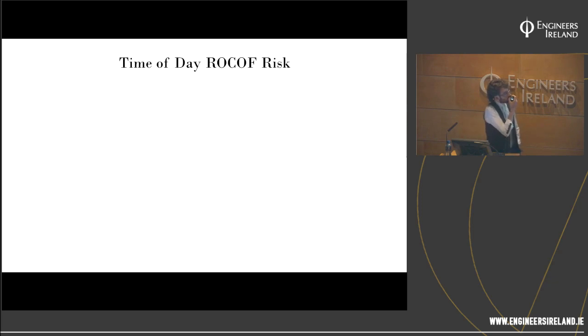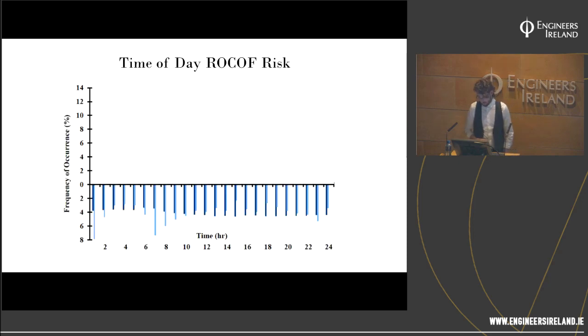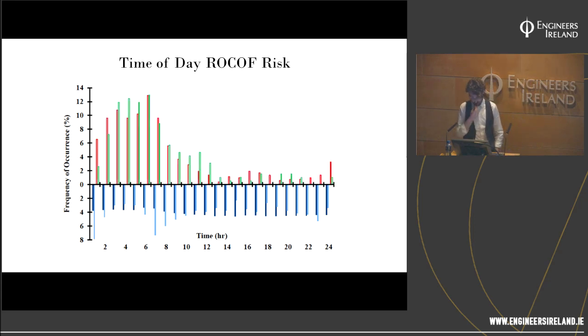You could also try to categorize the risk of rate of change of frequency by time of day. What I'm showing here is the probability for each hour, from 1 to 24 on average, of a loss of in-feed. The two different colors are for a band of RoCoFs between 0 and 0.5, and then from 0.5 above. You can see that the risk doesn't really change throughout the day. It's quite constant.